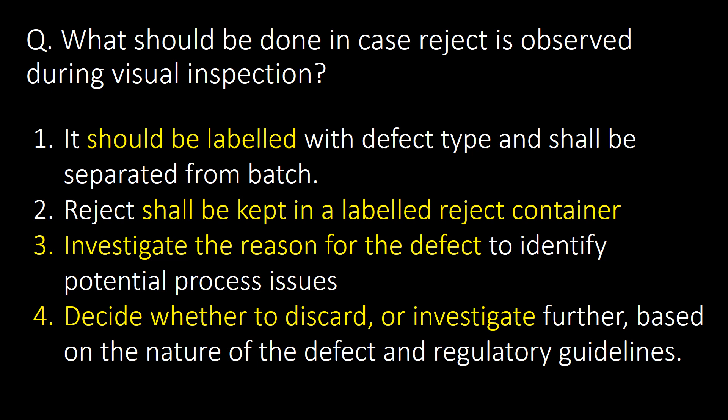What should be done when a reject is observed during visual inspection? First, it should be labelled with the defect type and separated from the batch. Second, the reject shall be kept in a labelled reject container. Third, investigate the reason for the defect to identify potential process issues. Fourth, and very importantly, decide whether to discard or investigate further based on the nature of the defect and regulatory guidelines.